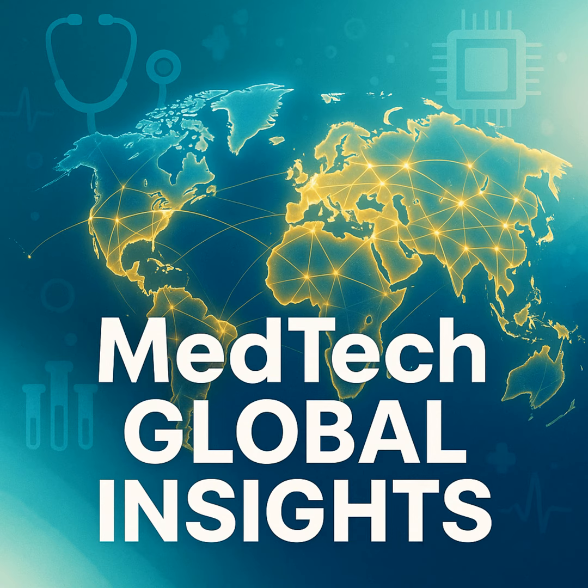Finally, we have Class 3 devices. These are the highest-risk products, often life-sustaining or implantable. This includes devices like pacemakers, artificial heart valves, and automated external defibrillators. The regulatory bar here is incredibly high, typically requiring a pre-market approval, or PMA, in the US. A PMA is a scientific and regulatory review to evaluate the safety and effectiveness of the device. It requires extensive data from clinical trials.